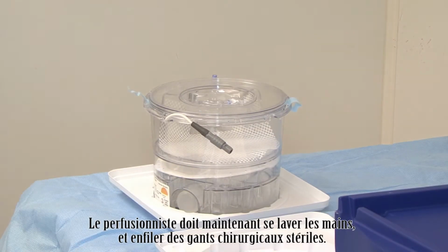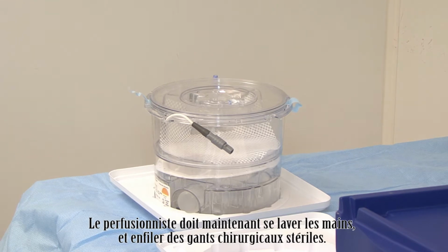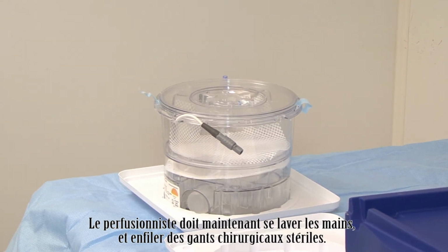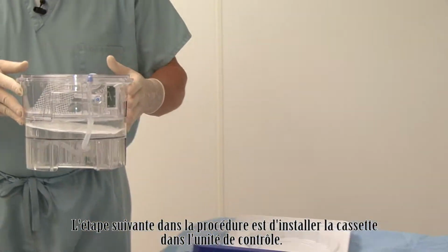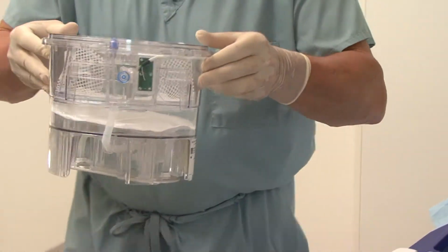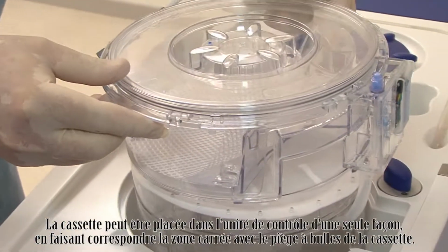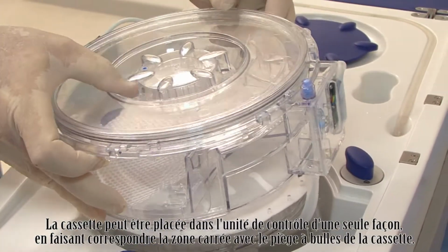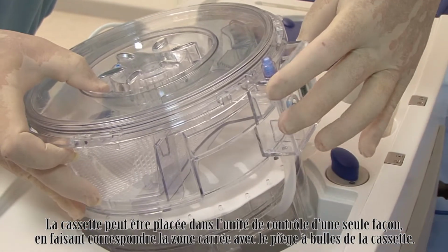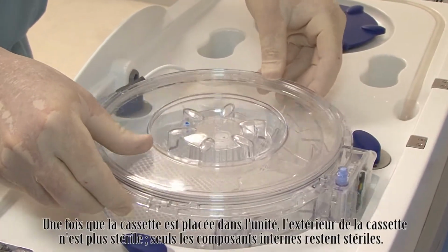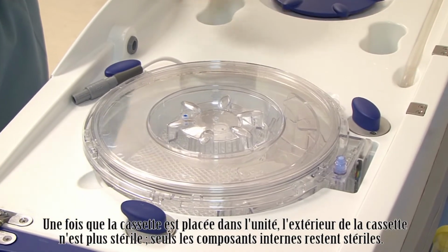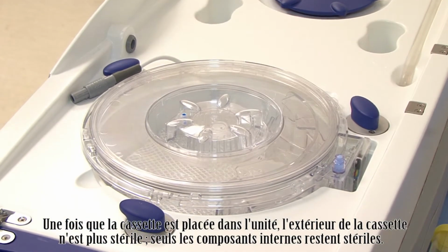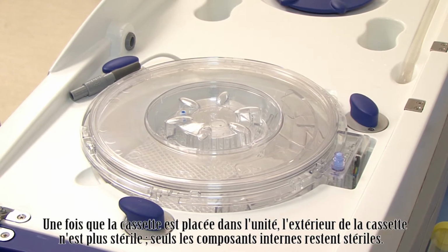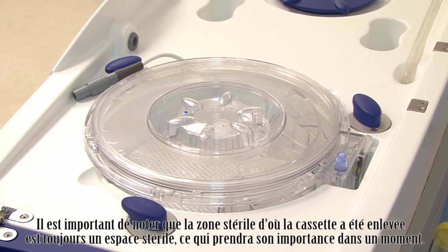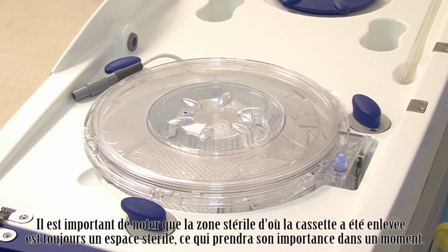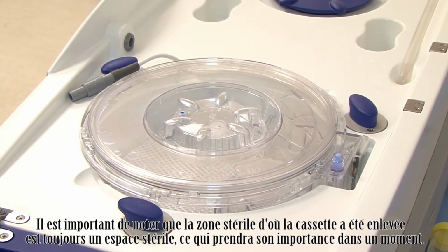The perfusionist should now go and wash his or her hands and don surgical sterile gloves. The next step in the process is to introduce the cassette into the control unit. The cassette can only be placed into the control unit one way, matching the square insert with the bubble trap on the cassette. Once the cassette is placed in the unit, the exterior of the cassette is no longer sterile. Only the internal component remains sterile. It is important to note that the sterile area where the cassette was removed is still a sterile space, and that will become important in a moment.